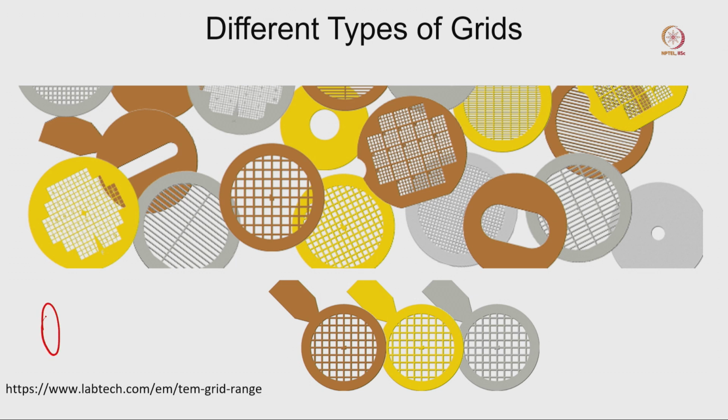You have an adapter and then you have a rod, there you have a pin which will recognize, then there will be an area, there will be an O-ring here which will directly connect to the microscope, and this is the place where your grid will go. So, this is the entire structure of your holder.